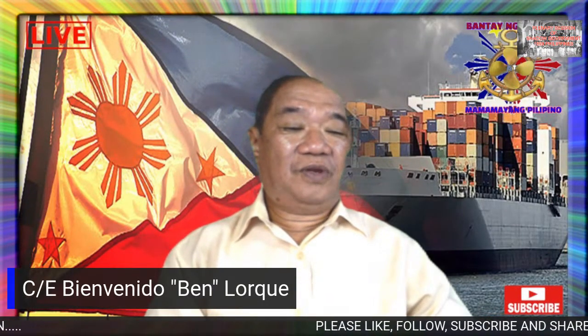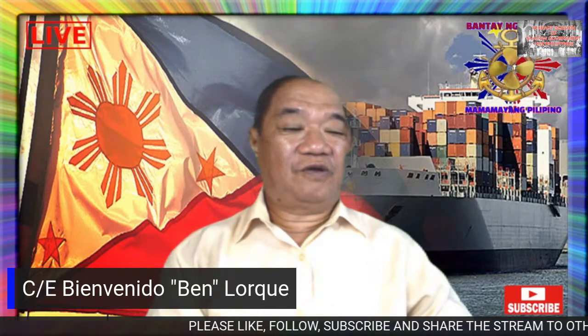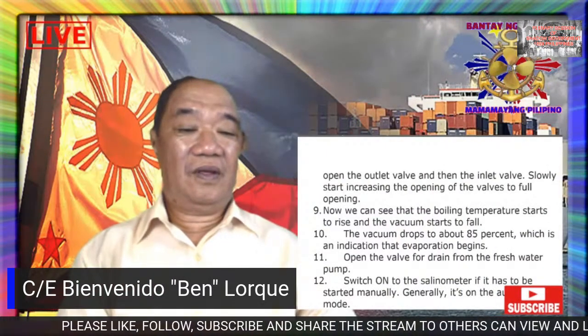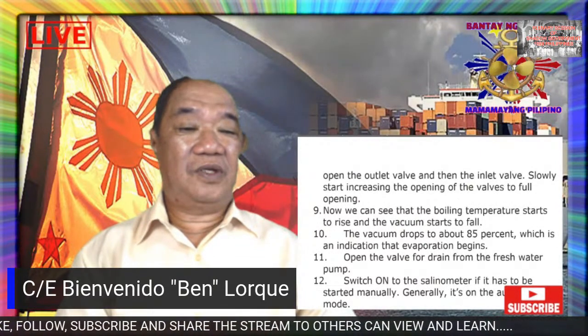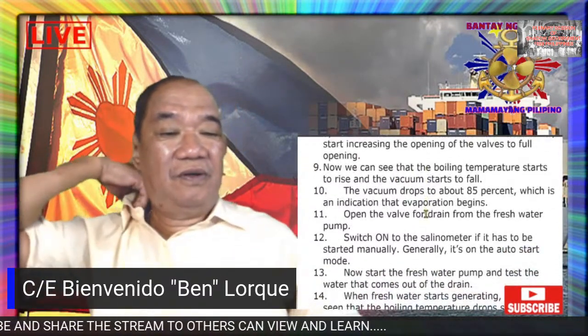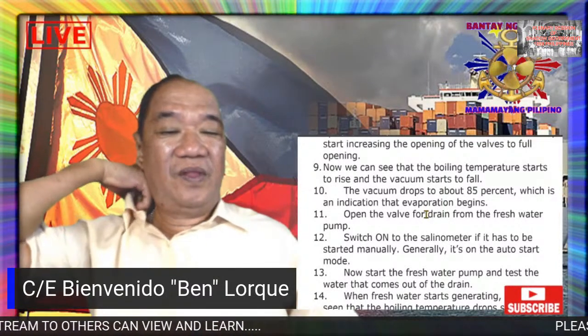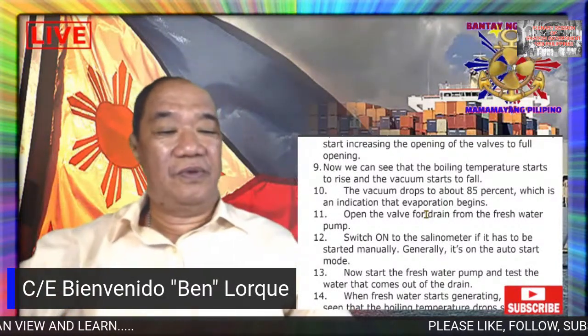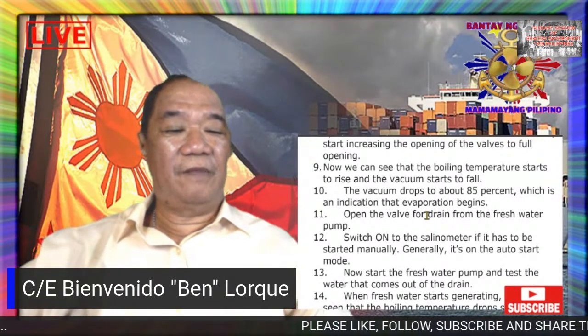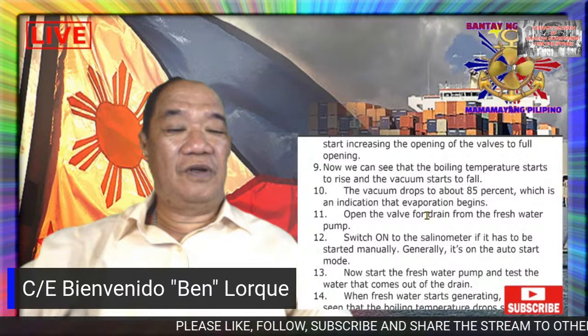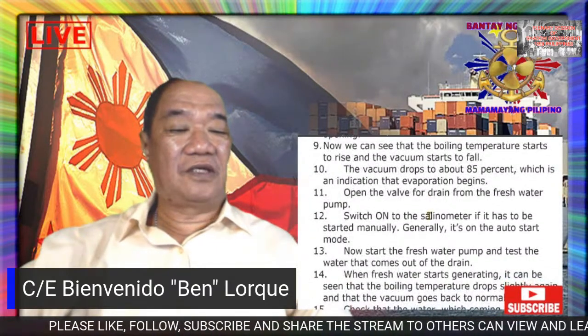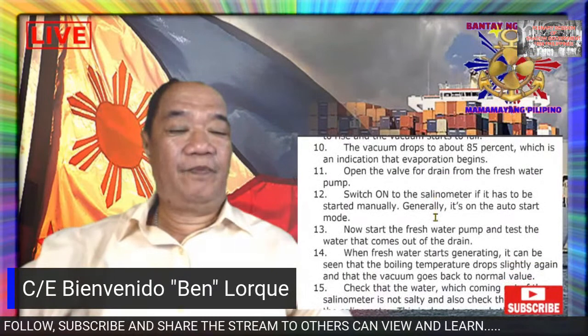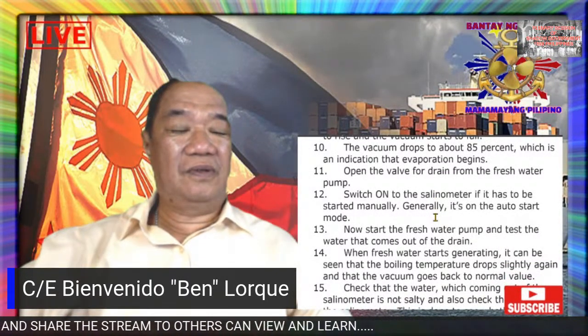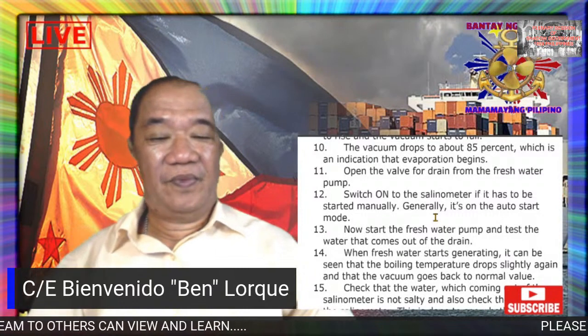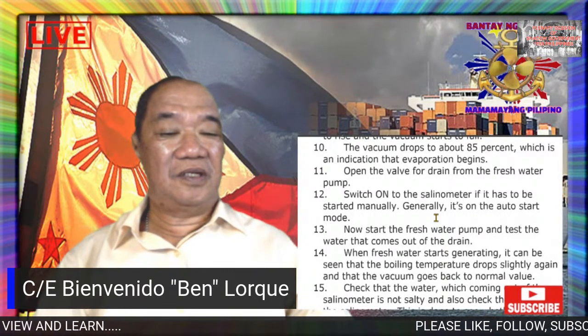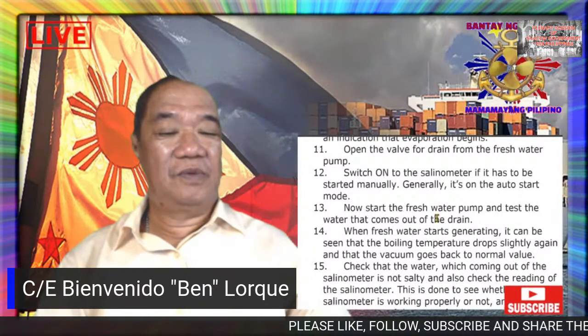So now we can see that the boiling temperature starts to rise and the vacuum starts to fall. The vacuum drops about 85%, which is an indication that evaporation begins. So open the valve or drain for the pressure from the freshwater generator pump. Switch on the salinometer if it has to be started manually, and generally it is in auto start mode. Now start the freshwater pump and test that the water comes out of the drain.